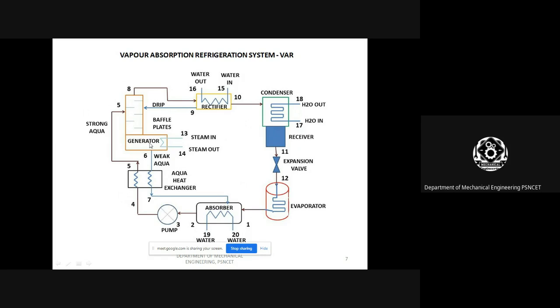Similarly, you see here in the generator, steam in and steam out. Here we are supplying steam, and the steam heat is passed on to the ammonia solution. Then it is passed on to the condenser through the rectifier. In this rectifier, there is a water in and water out, 15 and 16, right? So here also the same thing happens as in the absorber, and it goes to the condenser.